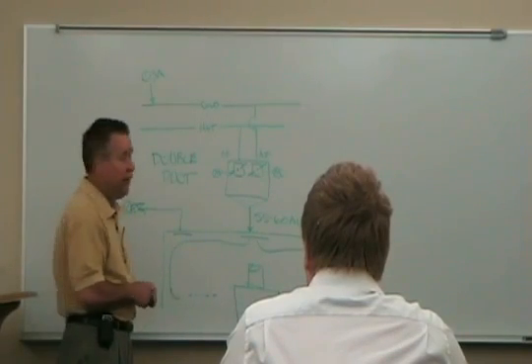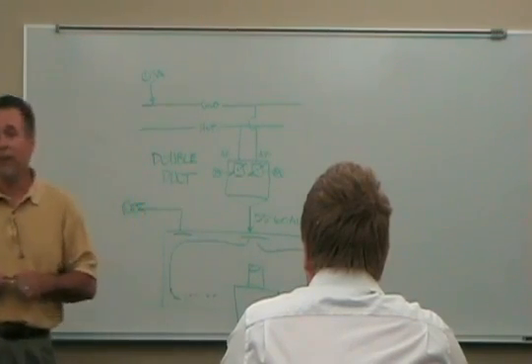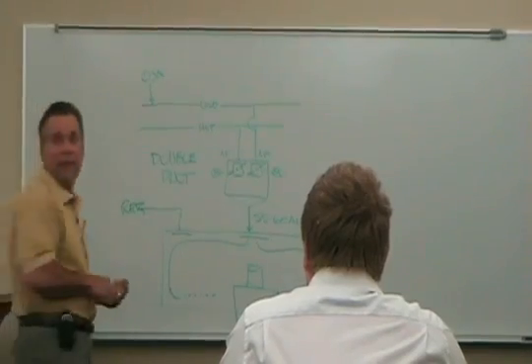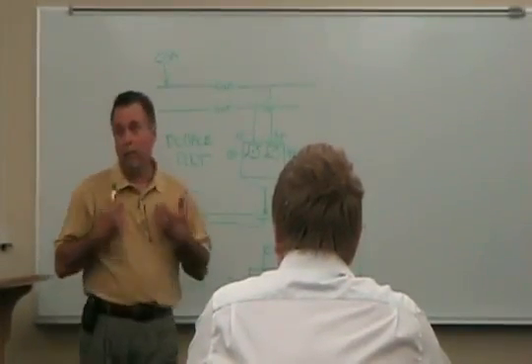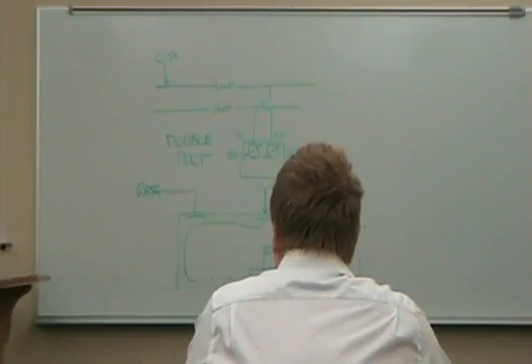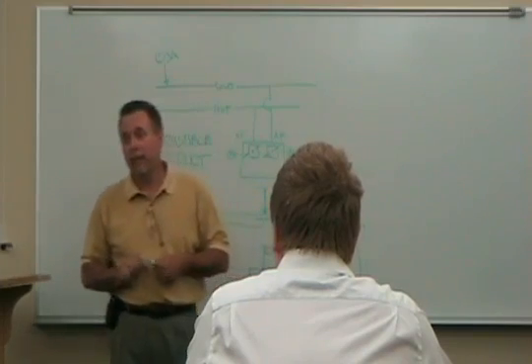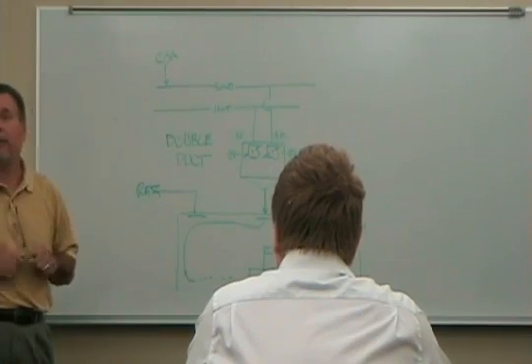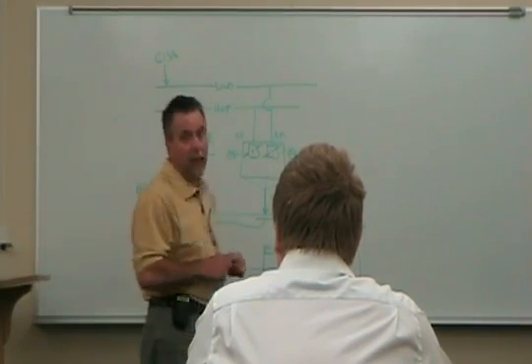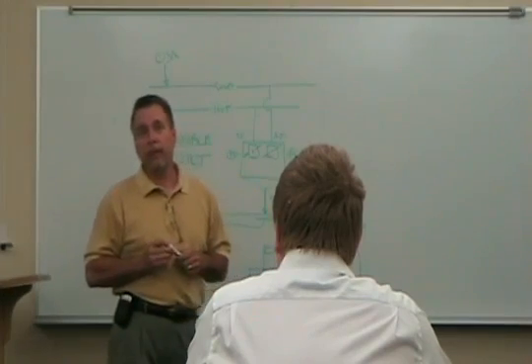Now the worst diffuser that you can use right there, can anybody guess what that is? Perforated face diffuser, which is used 99% of the time. Cold air will just simply fall right to the floor. And it's probably our portion of our fault, not informing engineers properly, but a good gentleman named Hank Wade Sr., 30 years ago, told the engineering community perforated face diffusers were the things to use in these newfangled VAV systems. And of course, Hank was God to most of the engineers. And at that time, maybe that was all that was available. But that's not what is available now.